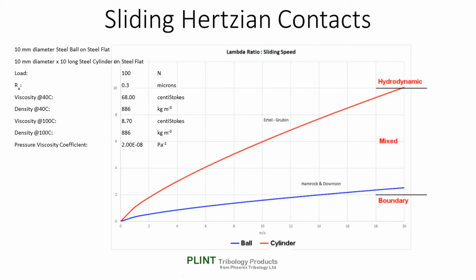Not to put too fine a point on it, with a ball sliding on a flat, even at fairly massive sliding speeds, it's unlikely to be operating anywhere other than in the boundary regime. Even with the line contact in this example, a sliding speed in excess of 2 meters per second is required just to make the transition from boundary to the mixed regime. There are not too many reciprocating tribometers that can achieve that sort of sliding speed.